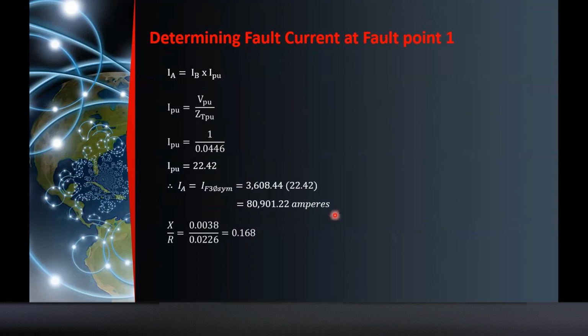So 80,901.22 amperes symmetrical fault. Therefore, your interrupting capacity ng circuit breaker at the secondary, ang rating mo is minimum, ibig sabihin, dapat hindi ako bumaba ng 80,901.22. Okay? So, alamin natin ngayon yung peak current naman. Ano yung peak current na mararanasan ng circuit breaker pag nagkaroon ako ng fault? Which is 0.5 cycle. So, kailangan mo ng short circuit power factor. Yung 0.0038, ito yung impedance mo, i-convert mo lang sa rectangular. Then get the ratio of X over R.